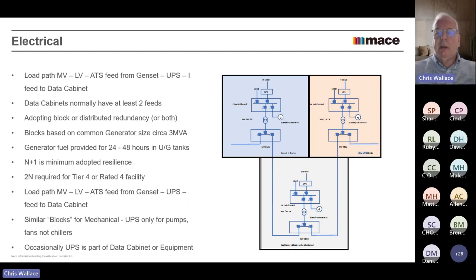The other thing is that typically for the generators, there will be a separate feed out to a common busbar, where you will have a load bank on the roof. And you might have a feed out from each of these LV boards as well. So the idea is that you can test the generators every month without taking the data center down, and that's what most of the customers end up doing. And because a lot of this is done in busbar rather than cable, busbar will become a significant expense as part of the overall project value.